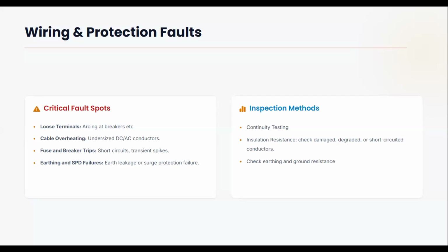Check earthing and grounding resistance. There are ways you can test to confirm that your earthing is good. You can do a load test. When you put a small load on the earthing, if it has failed, you won't even see the load come up. There are ways to use a capacitor to test. You use a capacitor to load the earthing. Then you can now use your meter.